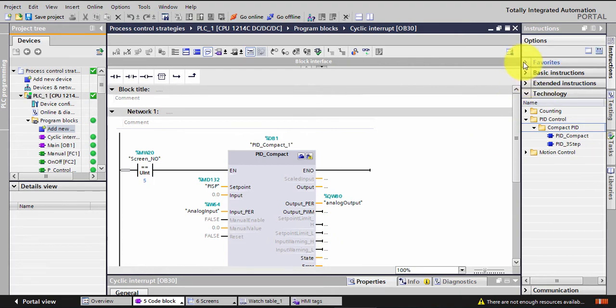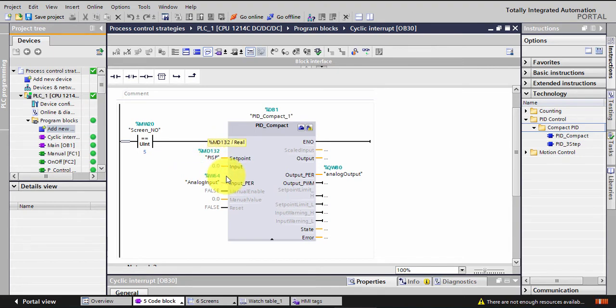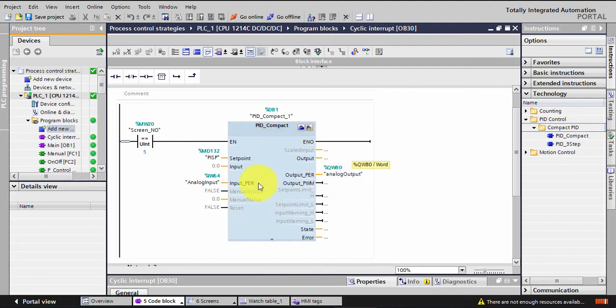I'm using PID Compact version 1 — if you're using version 2 it may be slightly different. For the setpoint, I'm entering my setpoint value and linking it to the HMI. For the input, I'm using the analog input directly with input percentage, and for the output, I'm using the analog output percentage since it's connected to the analog output. You can configure these by clicking the configuration window button.